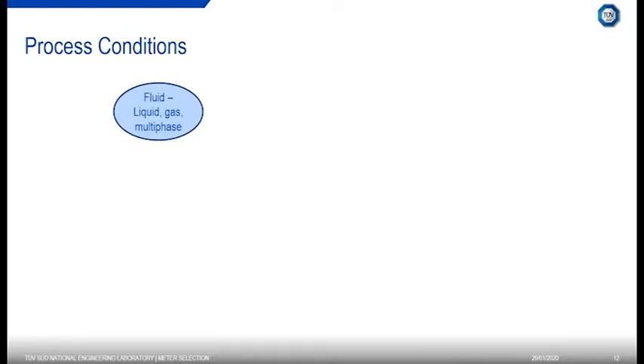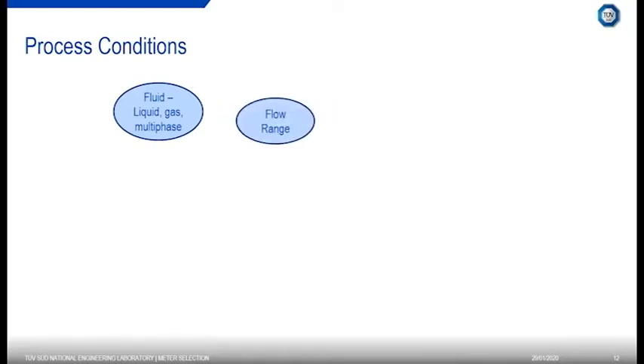One of the first things to look at is process conditions. You can imagine all the different industries requiring flow measurement having very different process conditions. Consider the fluid: is it a liquid, a gas, or multiphase — such as oil, water, and gas, or a two-component liquid like oil and water? There are a variety of things to consider, and this will greatly affect what flow meter you select. As this is an introductory webinar, we're only looking at single-phase today — multiphase might be a future webinar.